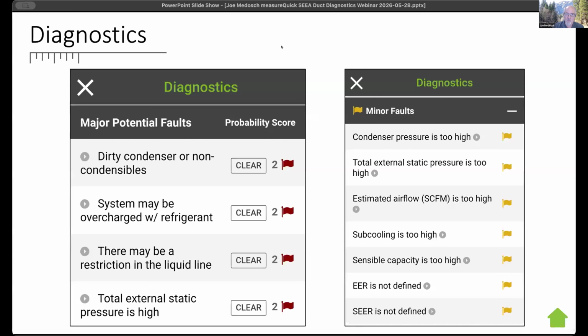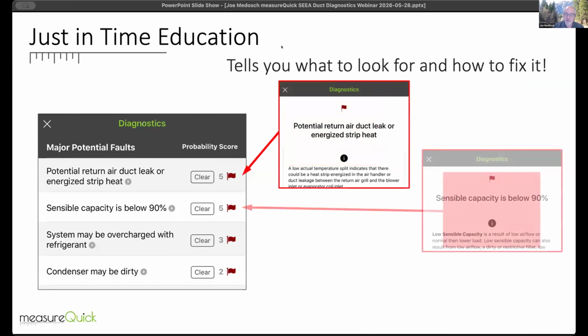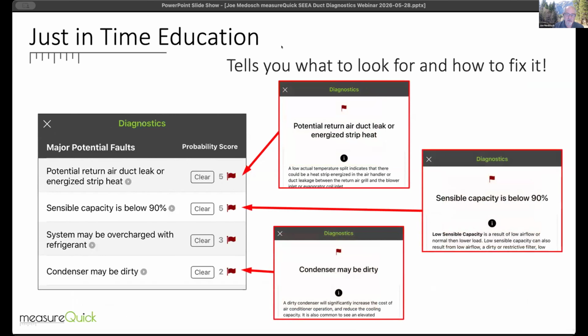And the one that's the most accurate and the most dynamic is actually the TrueFlow grid. There's no better way to measure true airflow than with the grid. These are some of the things you get there. Notice that the system may be overcharged, but at the top it says potential return duct leak or energized heat strip. It means that our temperature split is too high. These are all the things you're getting in MeasureQuick as part of their free diagnostics, and it's telling you what to do, what to look for, and how to step through those.